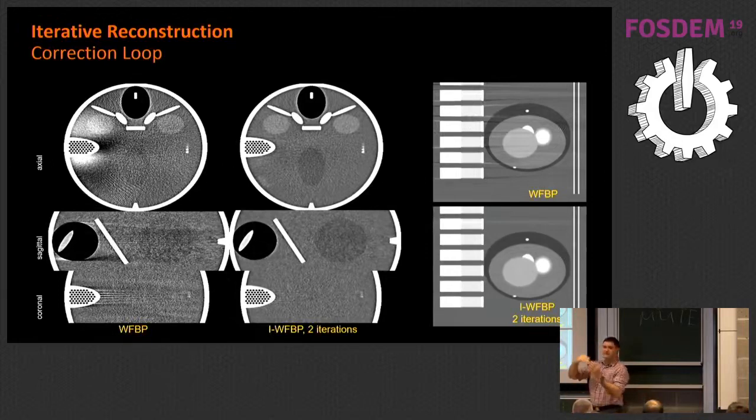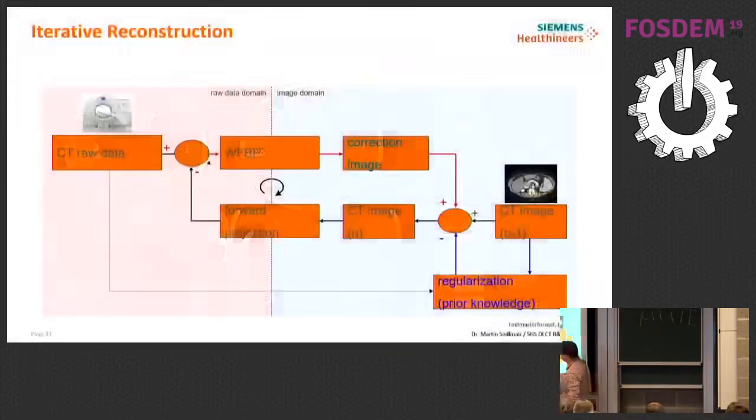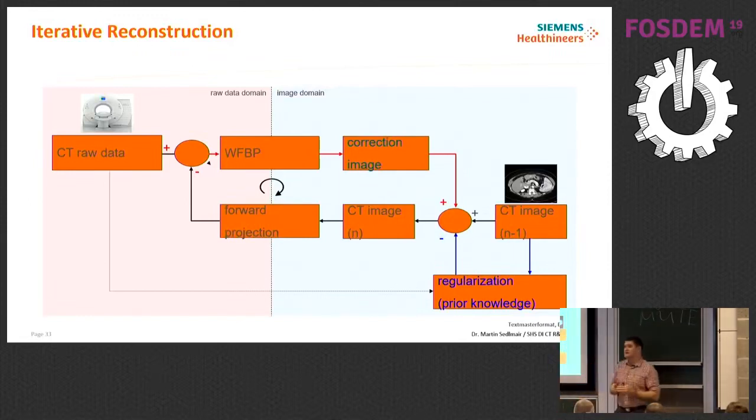So you invert the process, it's a little bit complicated, the process of reconstruction again. And then there is some sort of an image. So this is a loop where, with a few cycles, you try to recover the image quality and put also some prior knowledge in it. Because you know at the edges there is always a beam hardening, so you put prior knowledge in it just to recover these beam hardening effects.